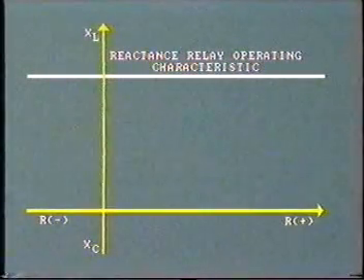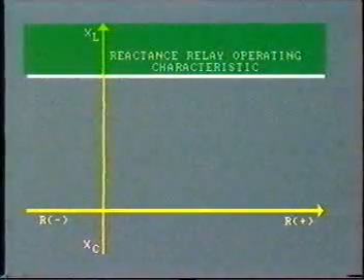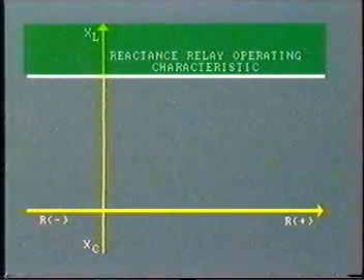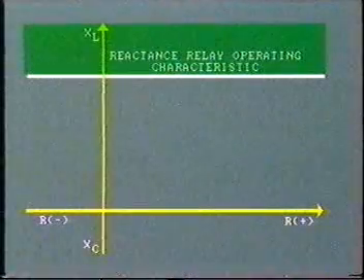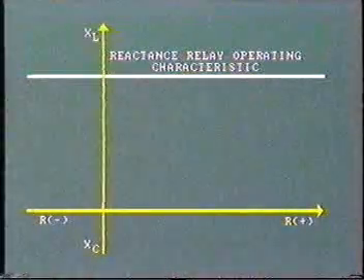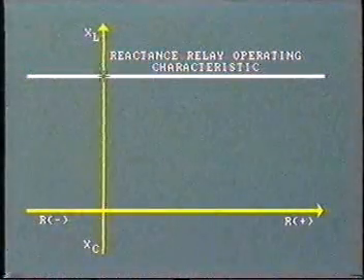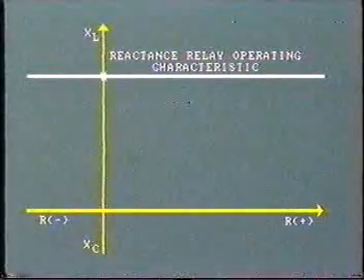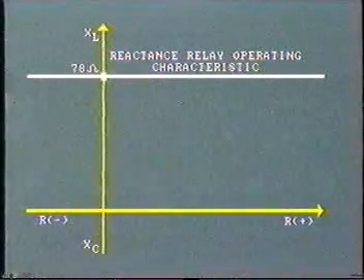During normal operation, the total reactance of the load and the transmission line will be above the operating set point. This will be 90% of 86.6 ohms, or 78 ohms in our example.